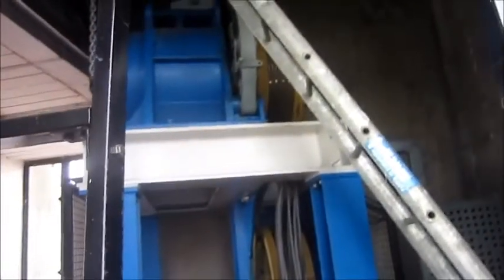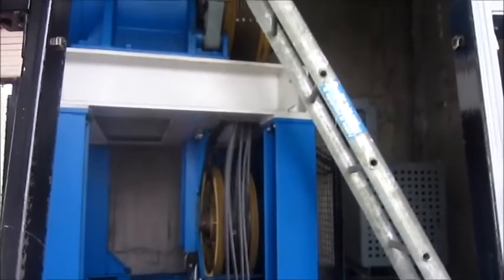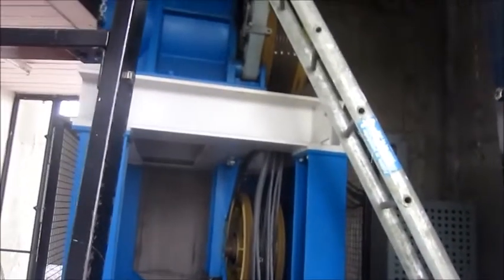So you know where those white building blocks are? If you follow back there, can you see that red van? Yes. There's a building to the right. This is just the motor, with cables connected. High speed lift. And that big lump there is the motor. The ropes are off at the moment because we've got to split the motor in half and rewind the windings on the stator.